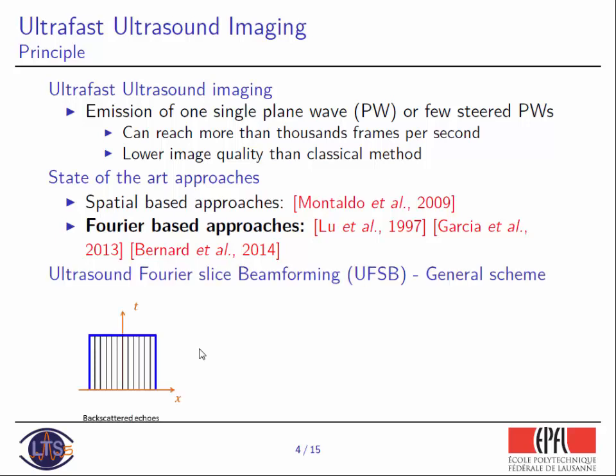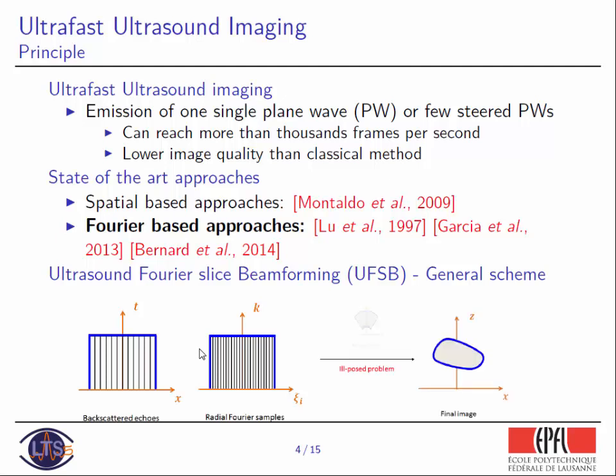It is called Ultrasound Fourier Slice Beamforming. So what is the general scheme? Let's suppose here is a picture of our image, there is a probe, and here are the different RF lines — our backscattered echo. The principle is: from this echo, we take the Fourier transform in time, then we tilt, simulating a delay at reception. We take the Fourier transform and sum. From different delays, we obtain different lines. Here is the k-space — we call these radial Fourier samples.